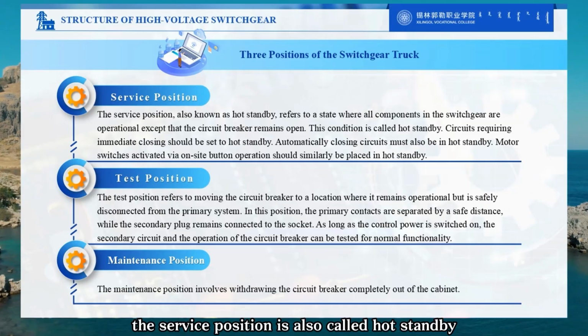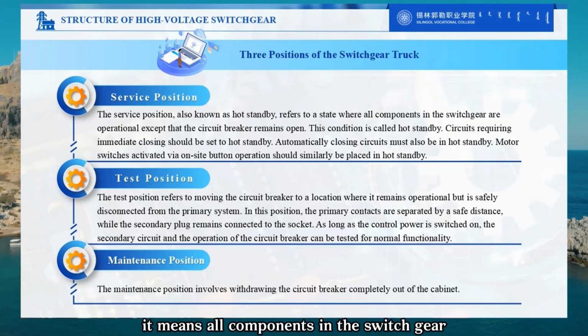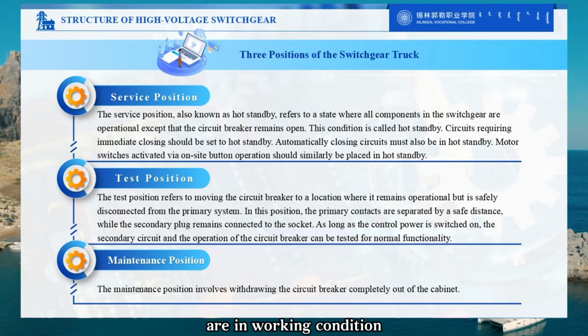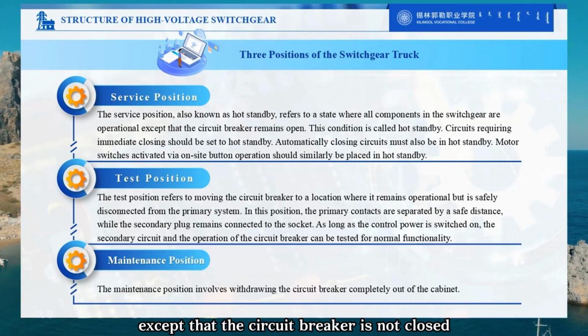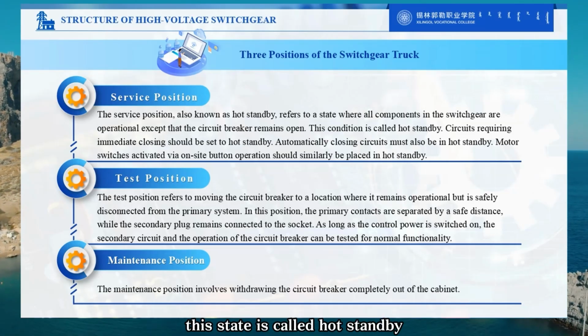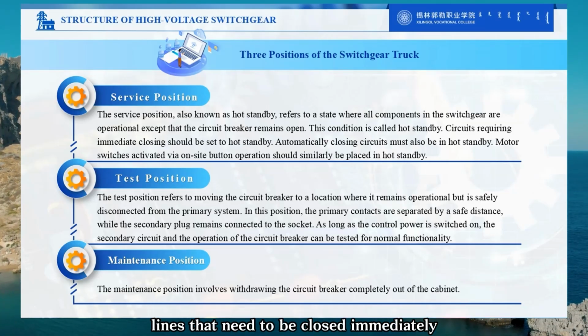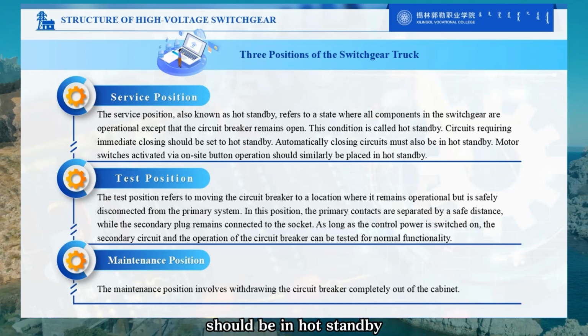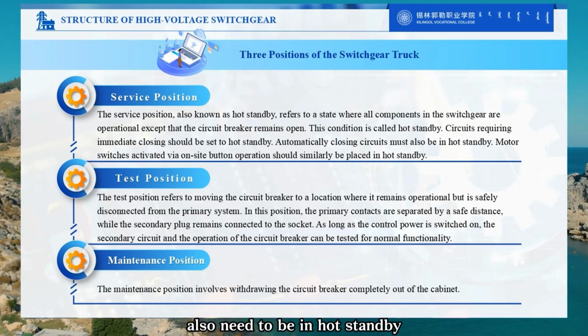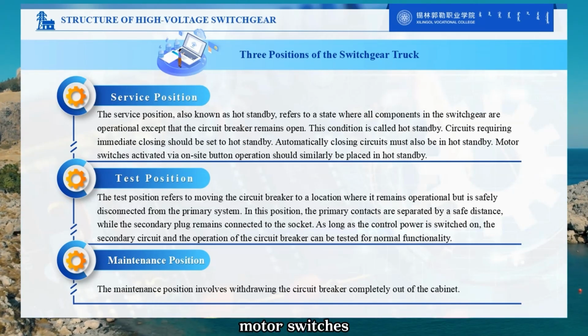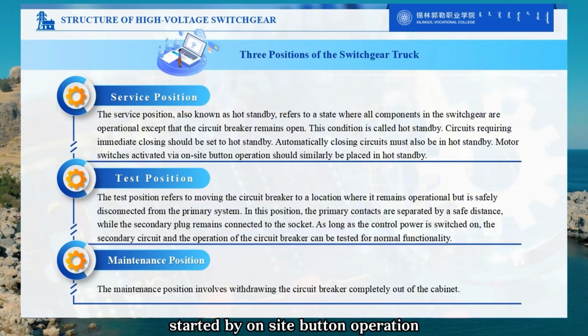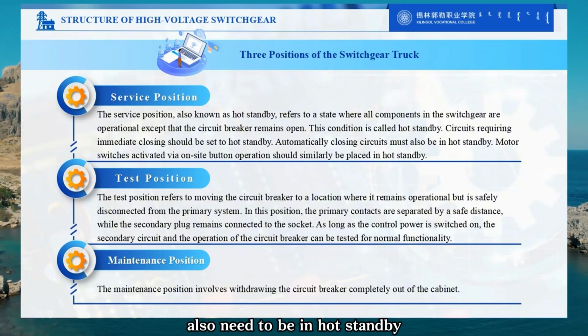The service position is also called hot standby. It means all components in the switchgear are in working condition, except that the circuit breaker is not closed. This state is called hot standby. Lines that need to be closed immediately should be in hot standby. Those with automatic closing also need to be in hot standby. Motor switches started by on-site button operation also need to be in hot standby.